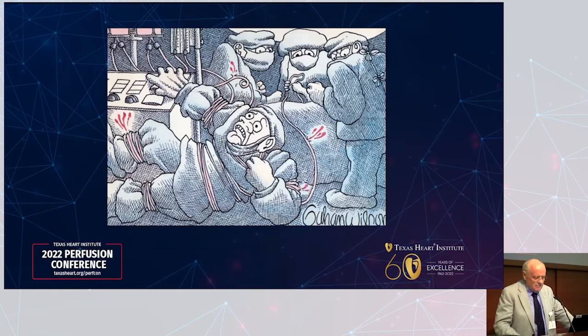The first centrifugal pump designed for cardiopulmonary bypass was by Harold Kletschka, M.D., and engineer Edson Rafferty. Dr. Cooley used the very first BioMedicus biopump on August 14, 1975 — on a 10-year-old Jehovah's Witness patient who did really well. The speaker saved that pump after the case, cleaned it, and has been using it in lectures for the past 45 years. This is considered one of the most significant contributions alongside the roller pump, because it led to the design and development of centrifugal pump technology by other companies.